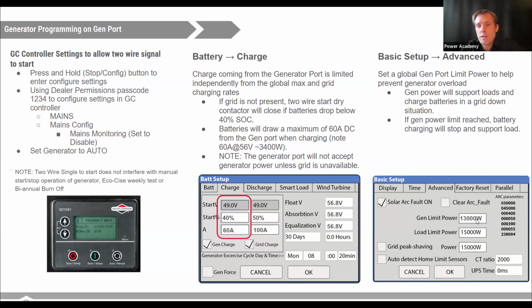So if I set it at 13,000 watts, then if the loads of my house go up to 8 kilowatts, it will reduce the charging rate on the battery down to 5 kilowatts. So we're not overloading the generator. And you can set this value lower as well. Typically with generators, you might want to set that a little below the maximum output of your generator, especially if you're up at elevation where you have to derate your generator output power, etc.